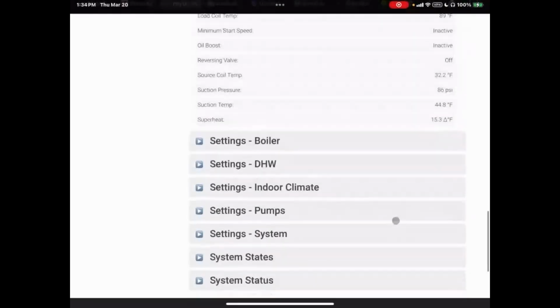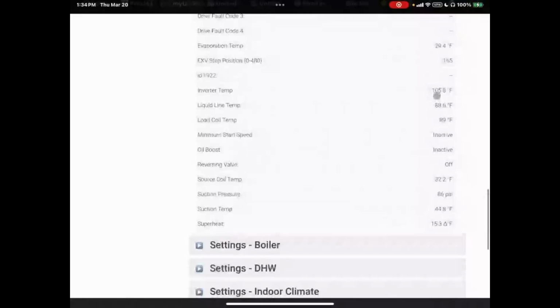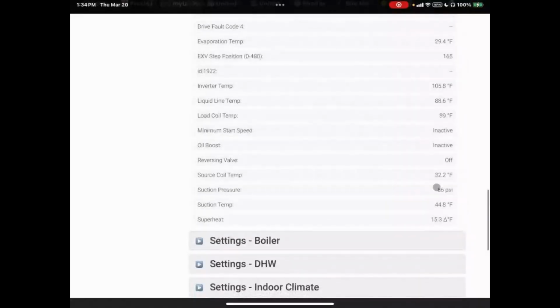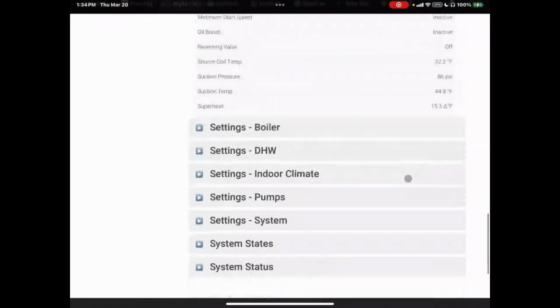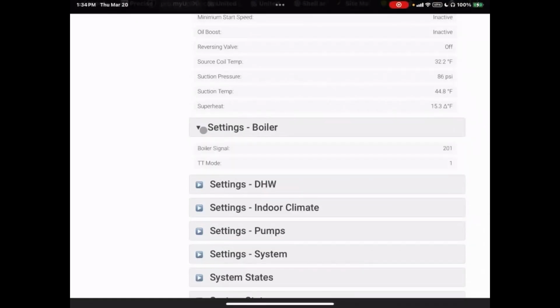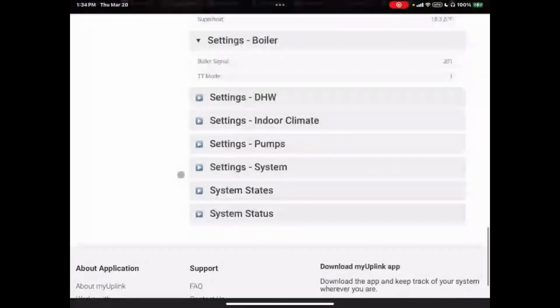On the web version, these values are not going to update live. You have to refresh your screen to update them. On the app version, they do update in real time. There is a slight delay, about 5 to 10 seconds from what's actually happening. But you can see here our boiler signal and a TT mode, because this is a dual fuel.